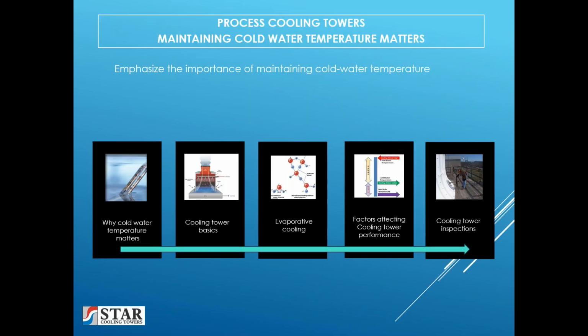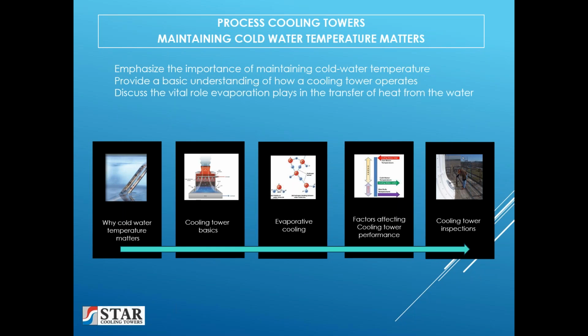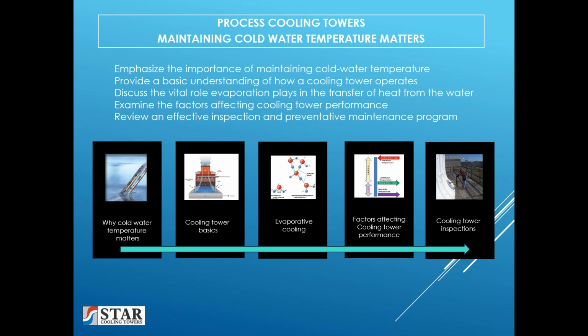The intent of this presentation is to emphasize the importance of maintaining cold water temperature in a water-cooled plant. Provide the cooling tower owner-operator a basic understanding of how a cooling tower operates and describe the various components. Discuss the vital role evaporation plays in the transfer of heat from the water. Examine the factors affecting cooling tower performance, such as wet bulb temperature and heat load. And finally, we'll review an effective inspection and preventative maintenance program that is essential in the safeguarding of the efficiency and lifespan of your cooling tower.